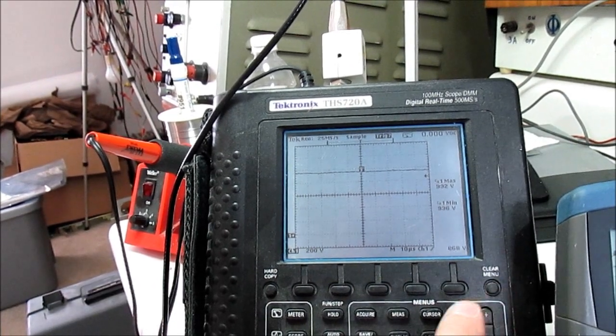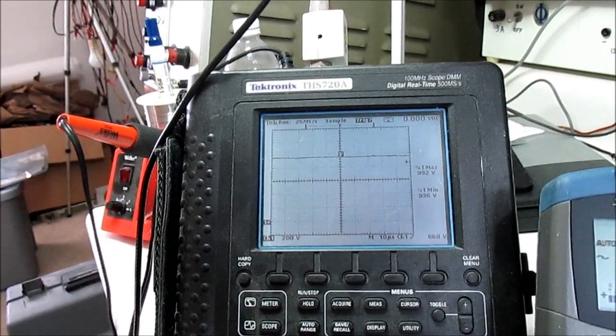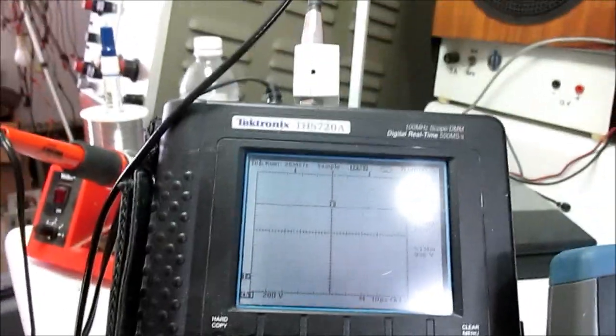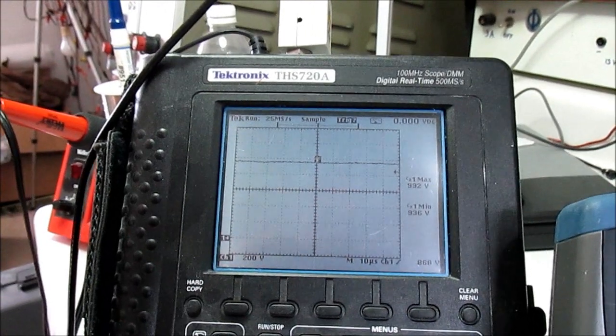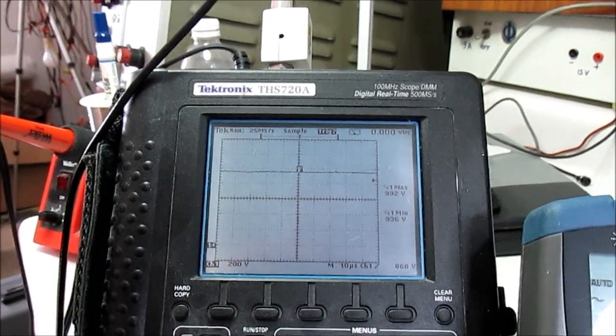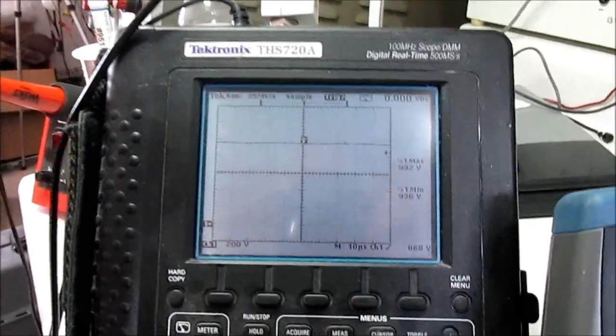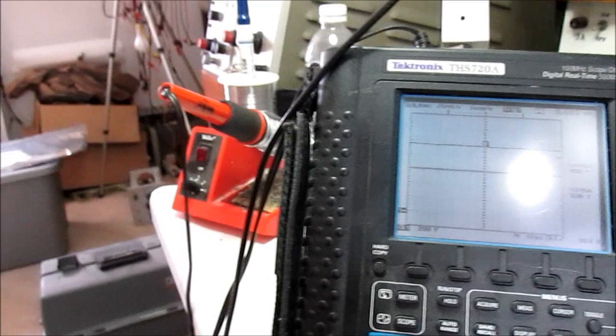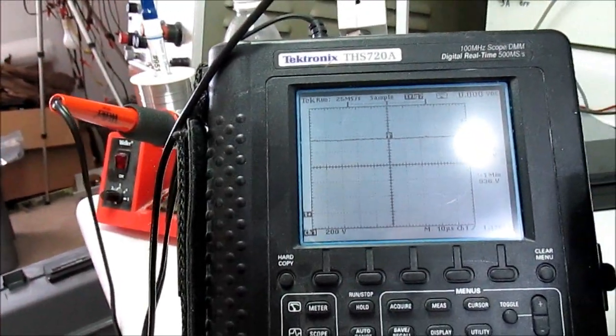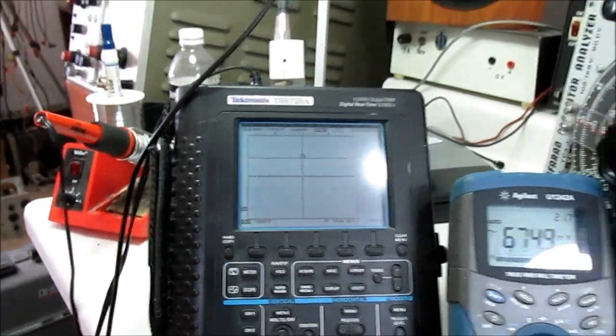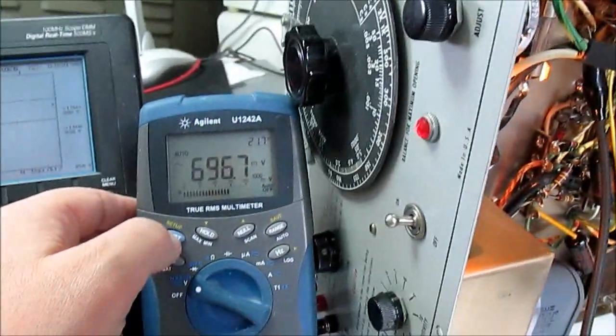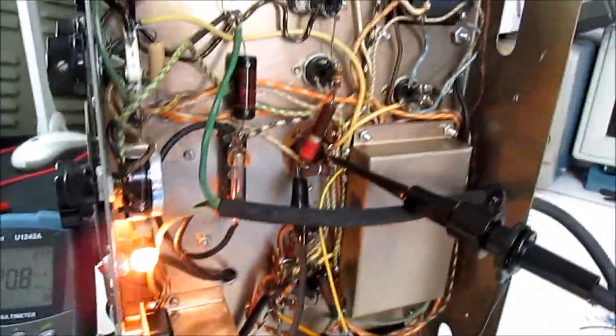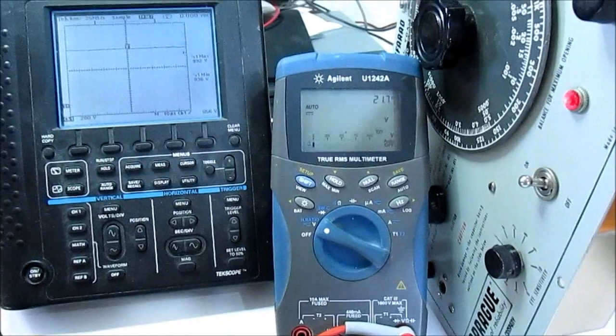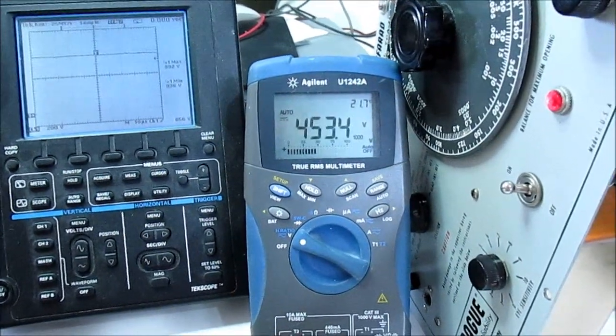Interesting. I don't know what's magical about the voltage there that would cause this meter to have a problem with the AC content riding on 450 volts or something. Maybe it's a problem with the meter. All right. So I'm not getting any triggering here on a spike waveform. On the other hand, I still don't like this voltage being so high that we have essentially the cap rated voltage, or very close to the rated capacitor voltage, at no margin. That just doesn't seem right to me.